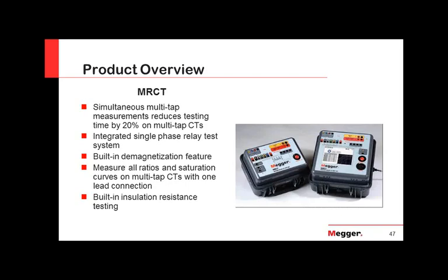And of course, instrument transformers. We cannot forget about the instrument transformers. When you are testing CTs, one of the things that you have to do, if you follow the standard C57.13.1, is run winding resistance testing. You need to run a saturation test or excitation current test. You need to run ratio tests.